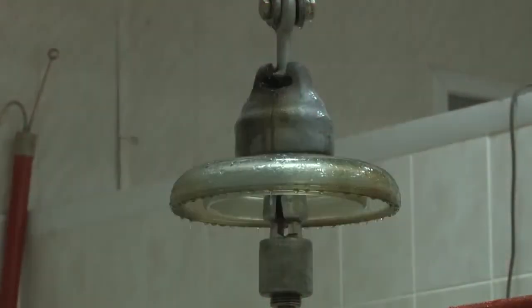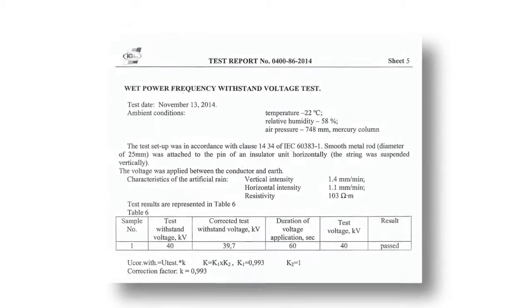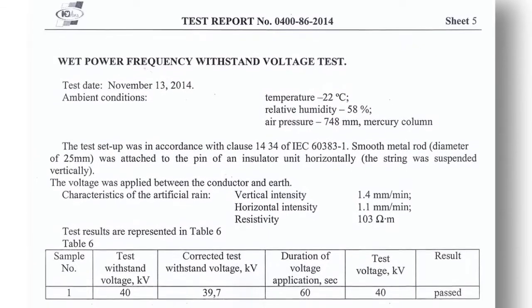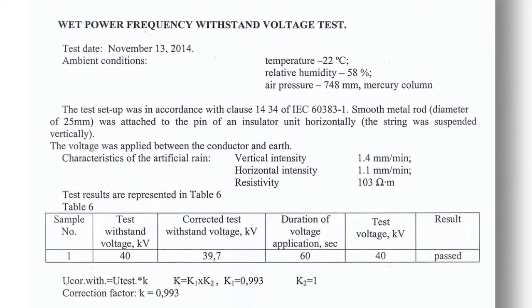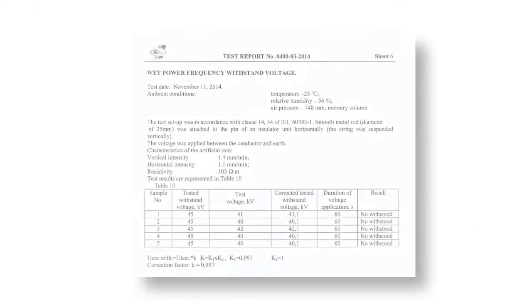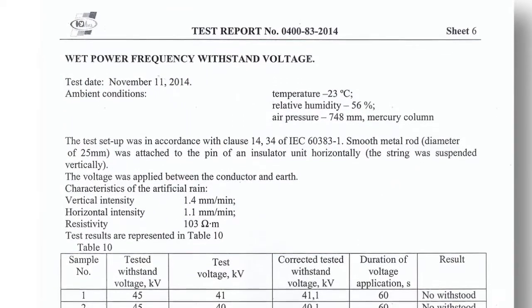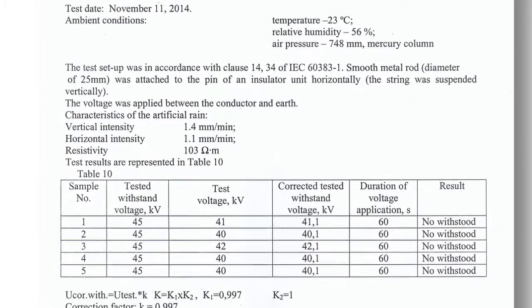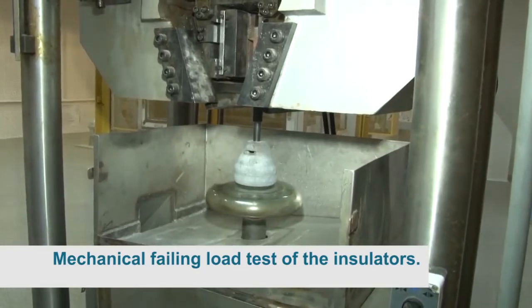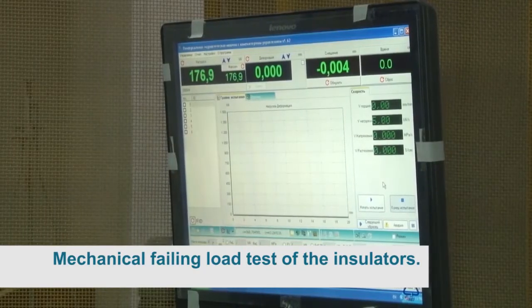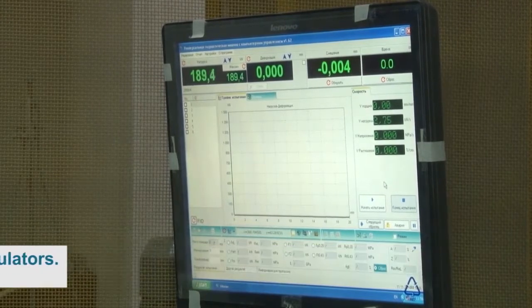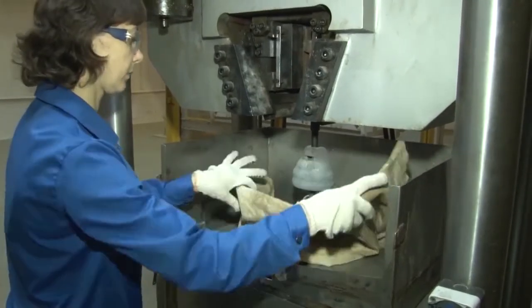An insulator of type PS70E was tested by application of standard voltage. The test voltage was 40 kilovolts. The application of voltage continued for 1 minute. The insulator of type PS70E passed the test. It complies with the IEC standard. Mechanical failing load test of the insulators of type PS12A and PS70E. The insulators passed the test because the mechanical failing load was higher than the standard load and no puncture occurred.